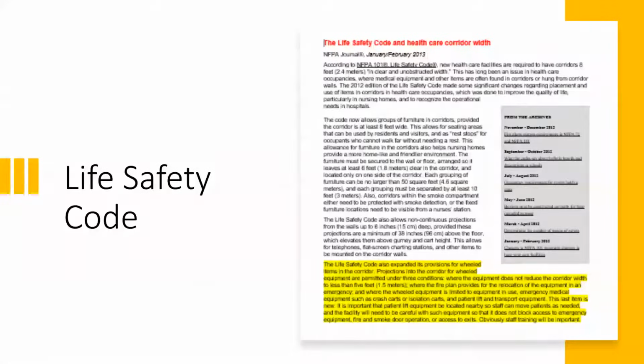Let's take a look at the life safety code. Projections into the corridor for wheeled equipment are permitted under 3 conditions: they cannot reduce the corridor width to less than 5 feet, you have to be able to relocate the equipment in an emergency, and wheeled equipment is limited to equipment that is in use, which specifically includes isolation carts, so make sure they're on wheels. As always, you cannot block access to emergency equipment, fire and smoke door operation, or access to exits.